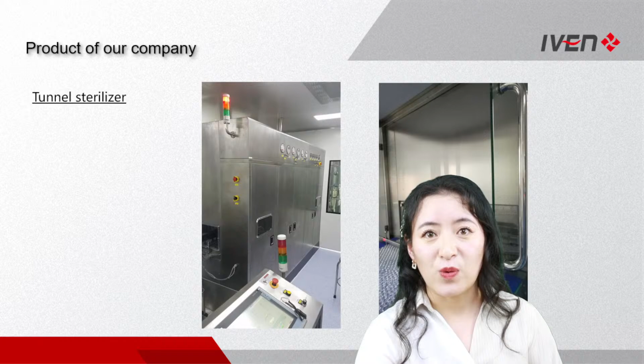Here, let me introduce our sterilizer, the tunnel sterilizer. The principle is like this. The laminar flow sterilization tunnel is used for washed vials or ampoules for dry sterilization and depyrogenation. It can reach a highest temperature of 340 degrees. It can adjust the motor speed to change the output by the rotation speed of the conveyor belt.